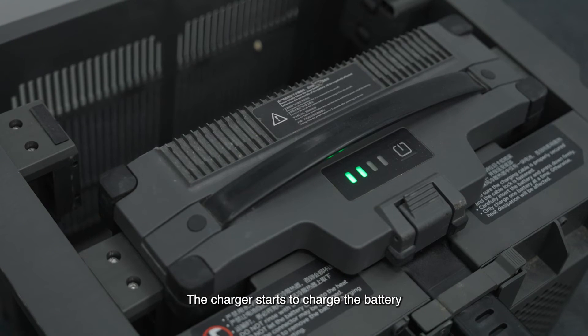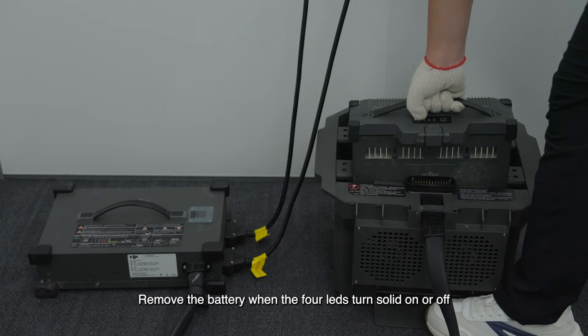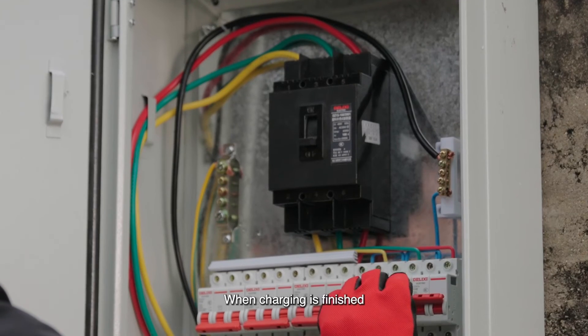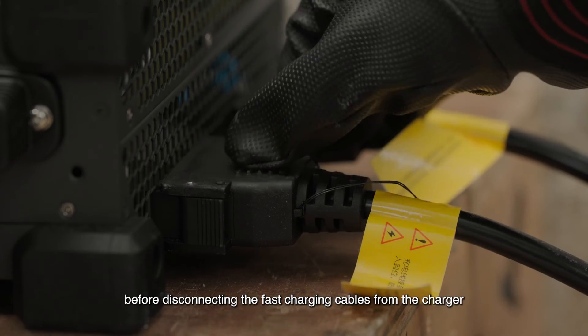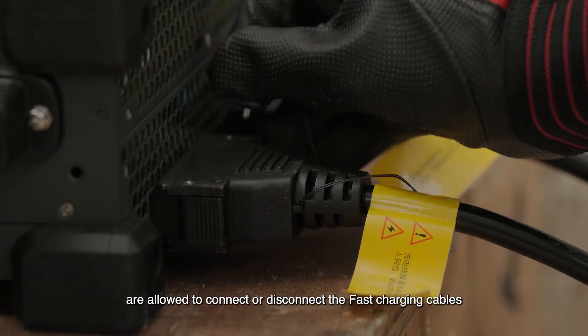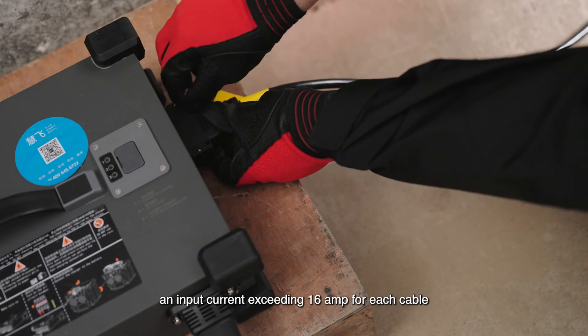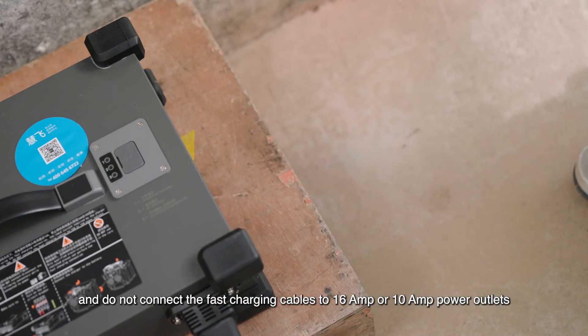The charger starts to charge the battery. During the charging process, the four LED lights on the battery blink in sequence. Remove the battery when the four LEDs turn solid or off, and put another battery inside the air cooled charger to charge. When charging is finished, turn off the air circuit breaker of the three phase power supply before disconnecting the fast charging cables from the charger. Only qualified electricians wearing insulated gloves are allowed to connect or disconnect the fast charging cables. Indoor fast charging is prohibited. Note that the charger requires an input current exceeding 16 amps for each cable; do not connect the fast charging cables to 16-amp or 10-amp power outlets.